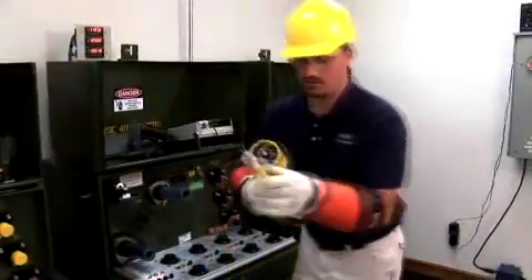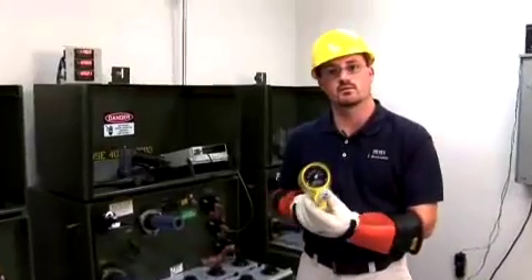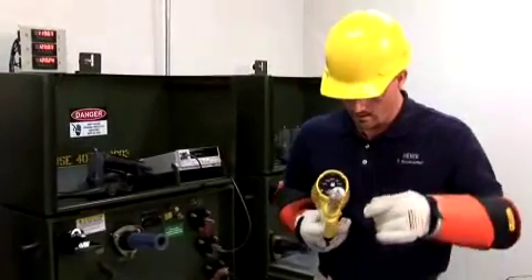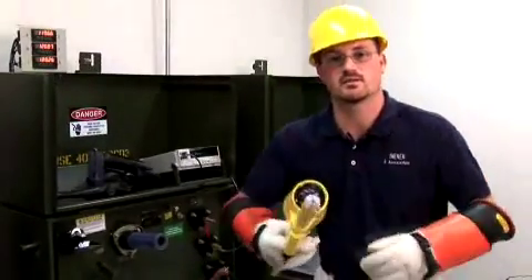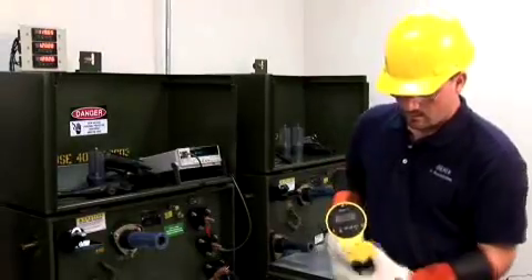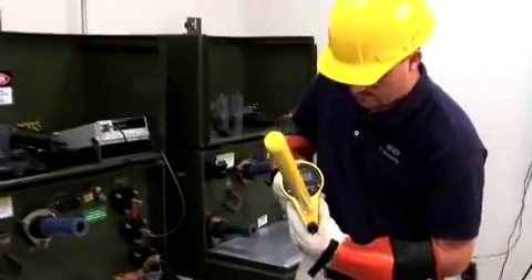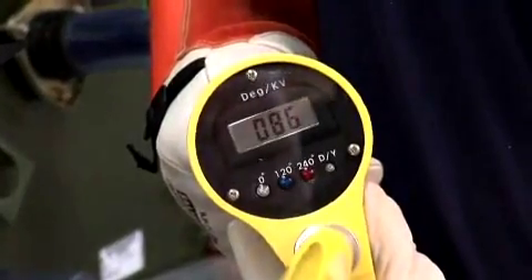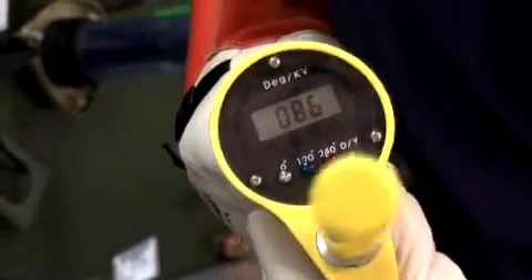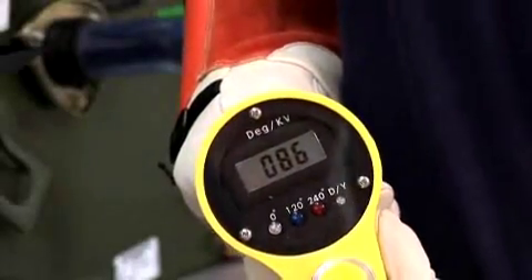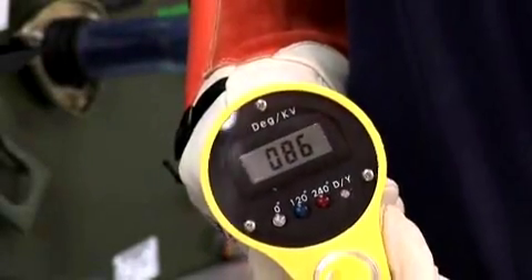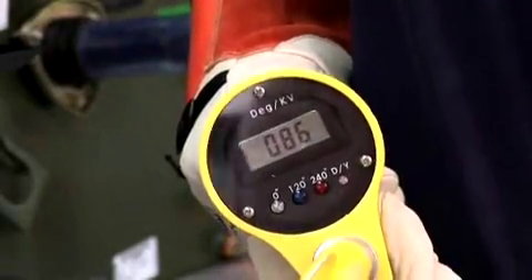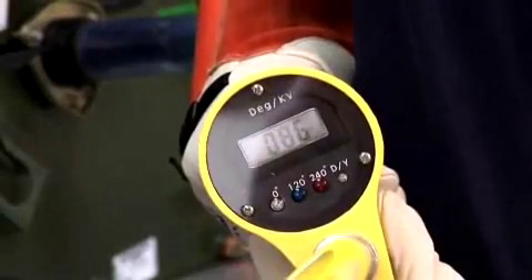The next position is the overhead position, which we'll be demonstrating outside with Joe. And the last position is the test position, momentary. In this position, it tests a light sequence. It momentarily displays 510 plus or minus 5 and displays the internal battery voltage. Right now we're measuring 8.6 volts. This verifies that the unit has sufficient battery voltage so you can begin work.